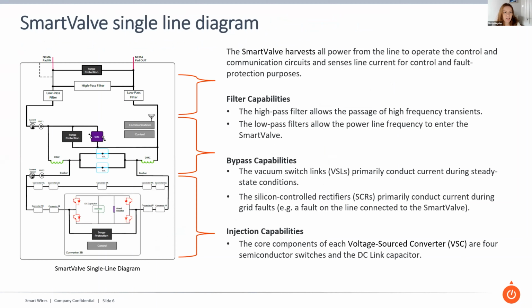So second last slide here, just to talk a little bit about the technology itself and how we use the power electronics. So in the bottom here, you can see the part of the smart valve, which in fact is where we inject the voltage. So we use these IGBTs to control the charging and discharging of a DC capacitor, which gives us our voltage wave. We can control the timing of them to minimize the impact of harmonic distortion on the transmission system. And we can control the magnitude of the voltage injection from 0 up to the maximum voltage injection from this device and anywhere in between. And so that is independent of the line current. And that's a significant flexibility that you don't obtain with a number of other technologies like series capacitors.